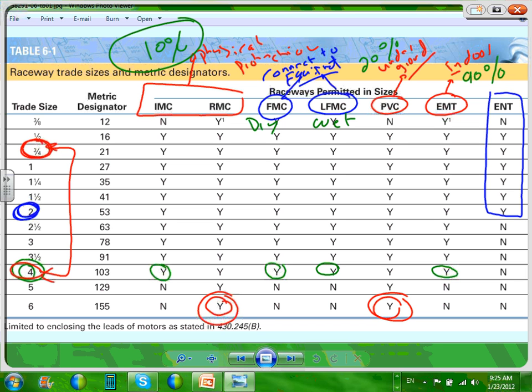Let me give you an example, guys, not for ENT, but for PVC use. Wastewater treatment plants have a lot of gases, and if you use rigid or EMT there, it will eat that baby. You wouldn't find it after maybe 10 years, it will be completely rusted. So what they use in wastewater treatment plants, because they need the rigid for physical protection and they need the corrosion protection, is they marry the RMC to the PVC.